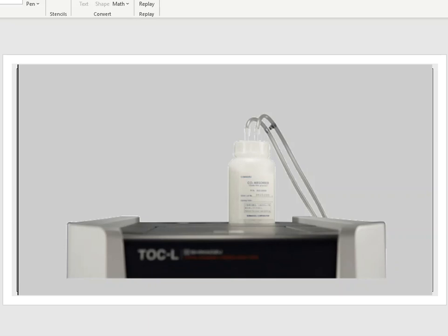So that means that you're just going to have to kind of trust it. You're going to have to look at what kind of samples you're running, get a good idea of how much CO2 is getting absorbed, and how long these crystals can actually last you as an individual. And then you put a routine maintenance in place where you can begin to exchange this bottle.